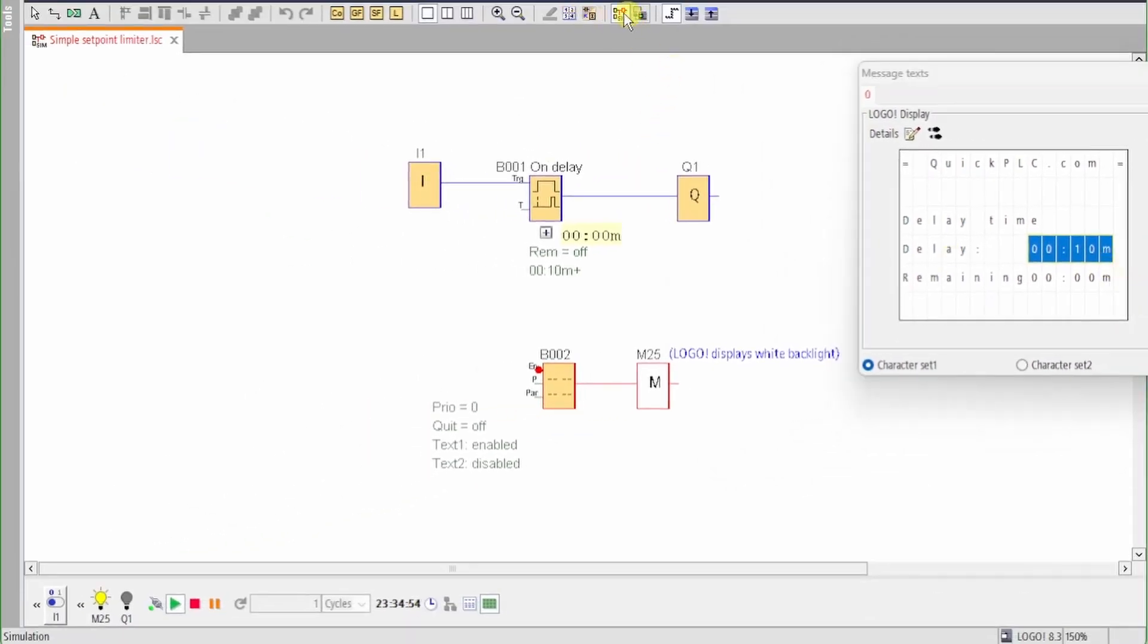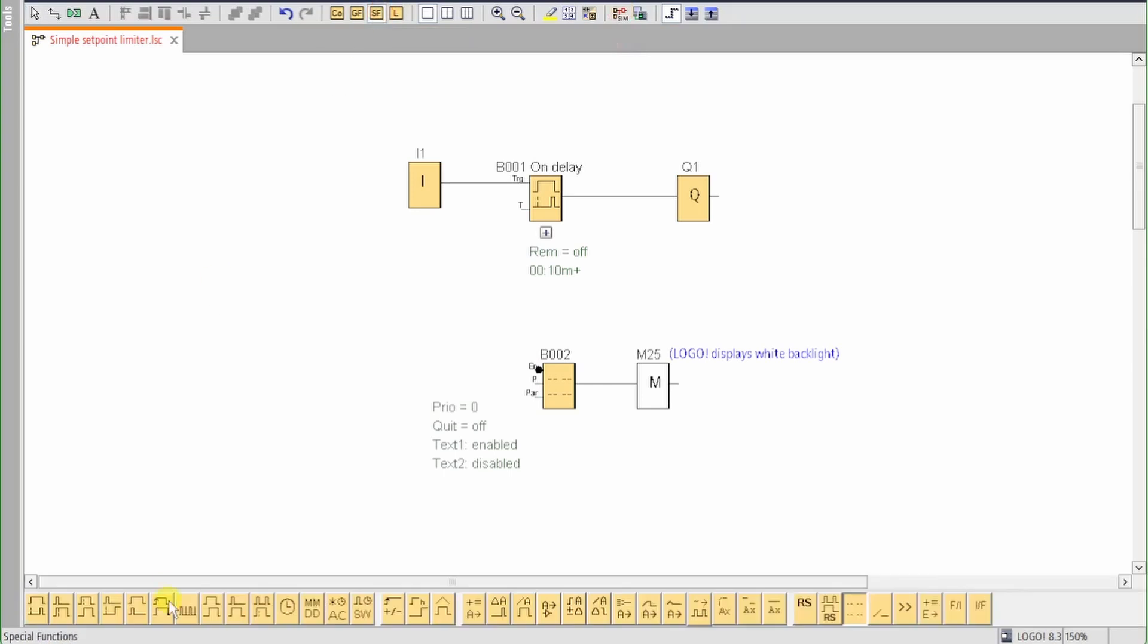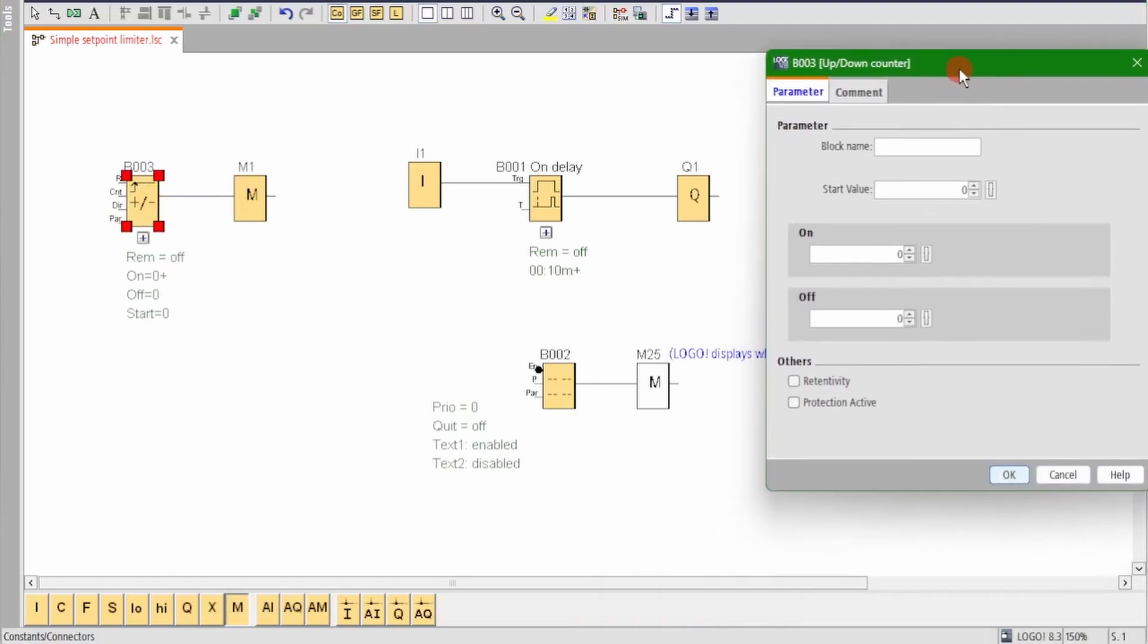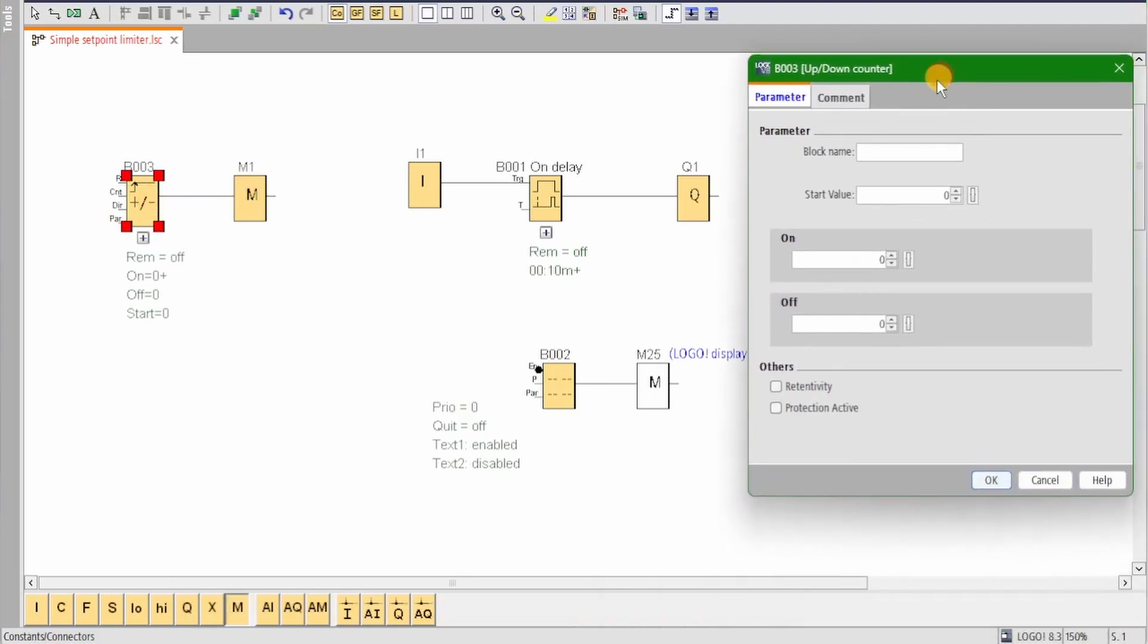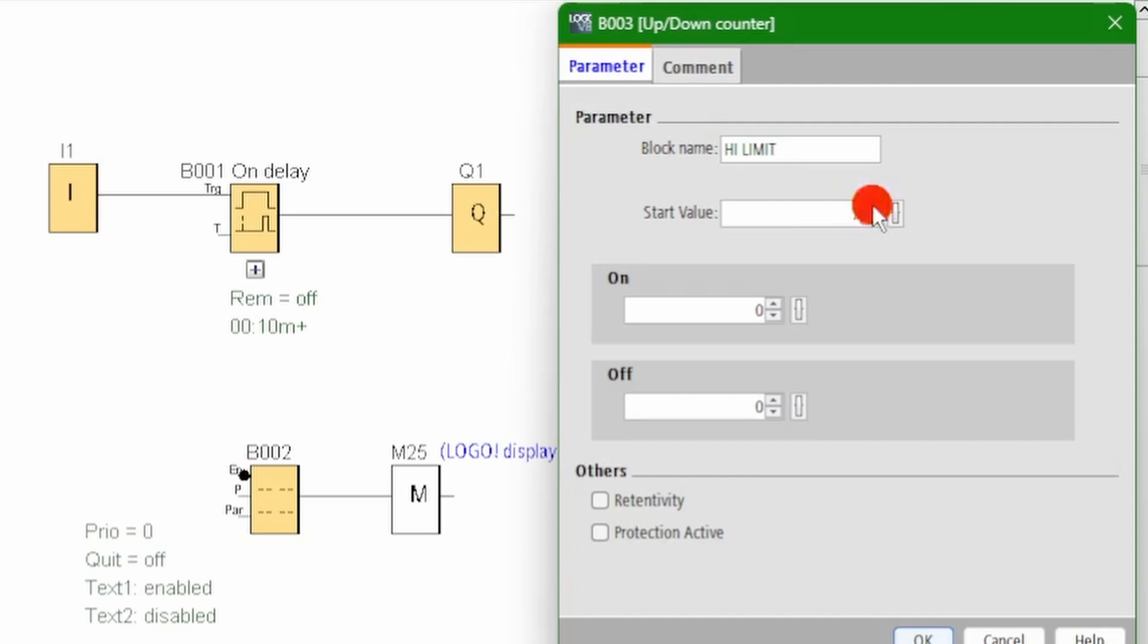We'll add an up down counter and the plan here is that if the count value ever reaches nine, we'll reset the counter to eight. We can't loop the output of a function block directly back to its input, so we'll add an M flag to do this. Set the start value to eight, set the on value to nine, and the off value to eight.